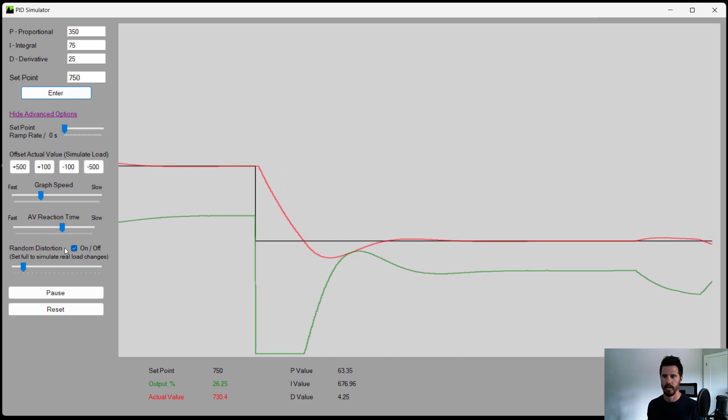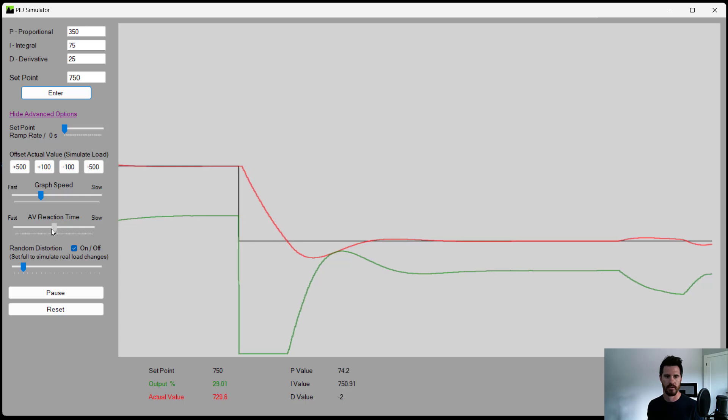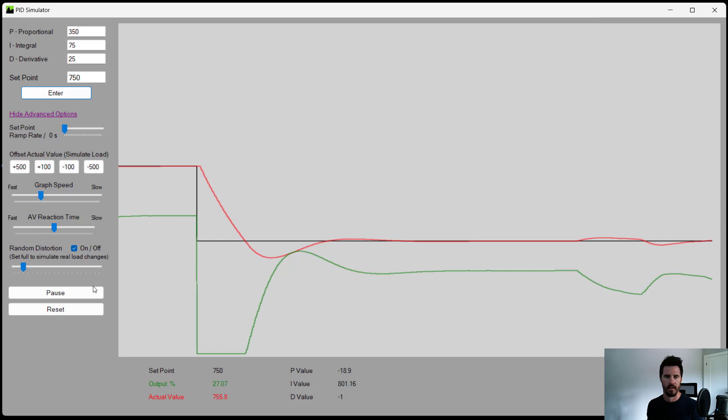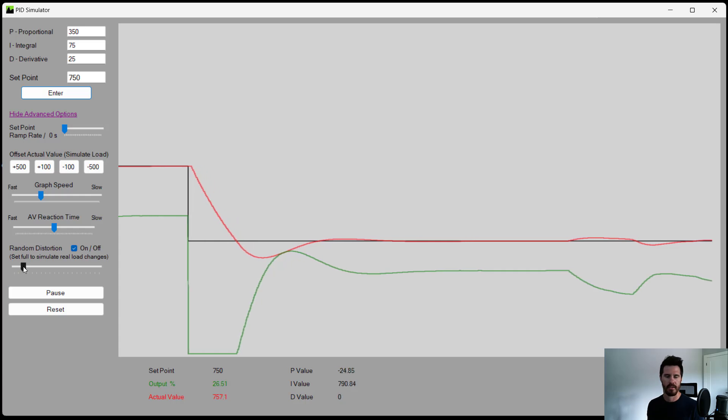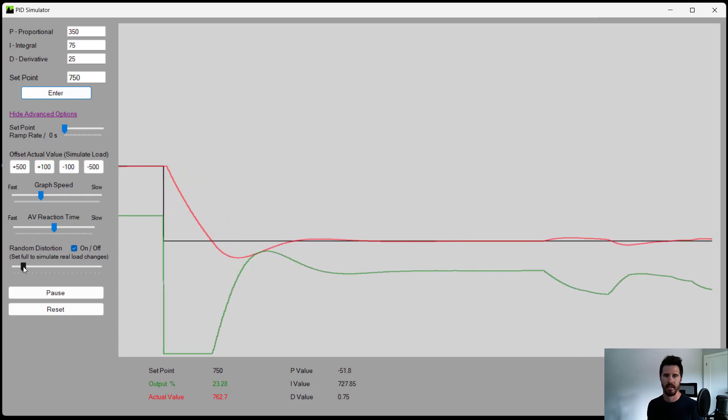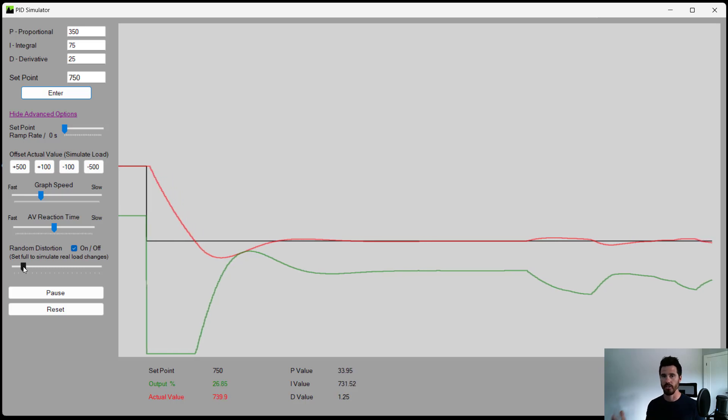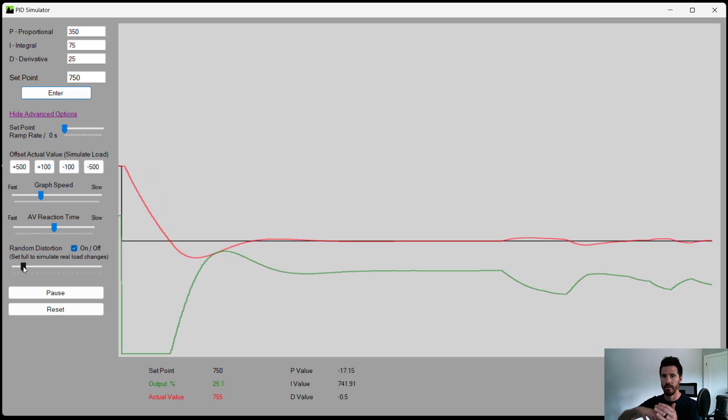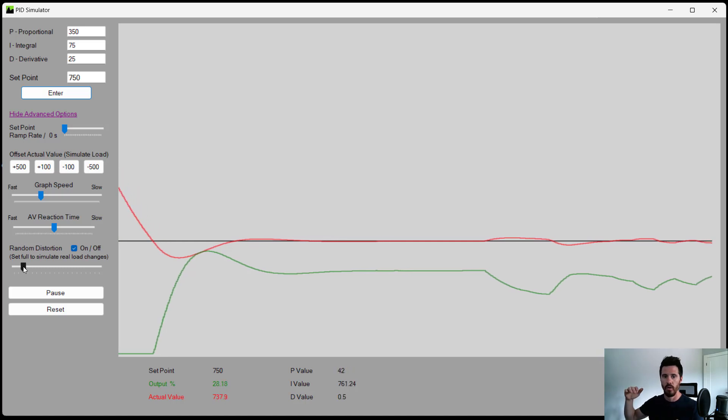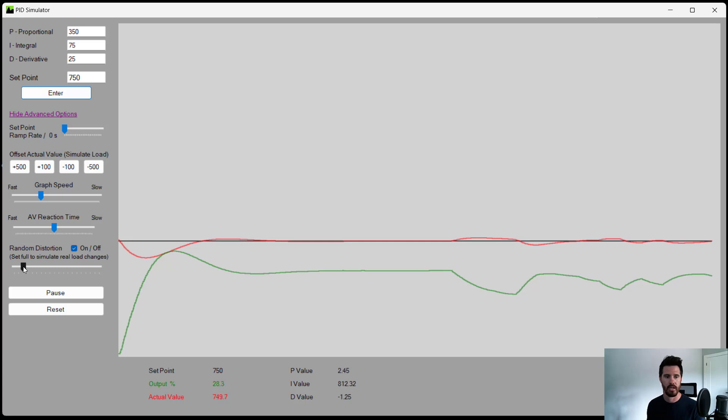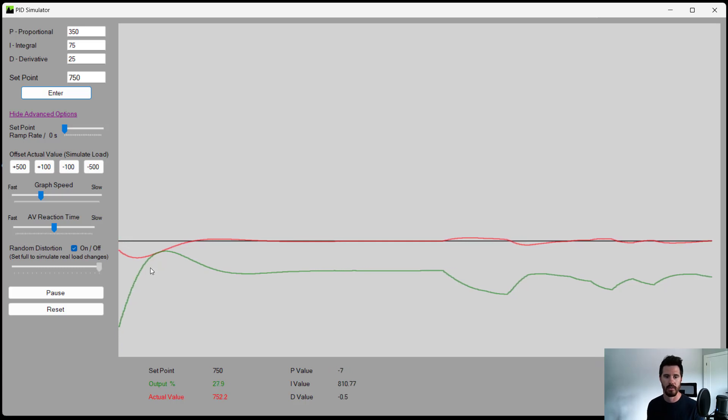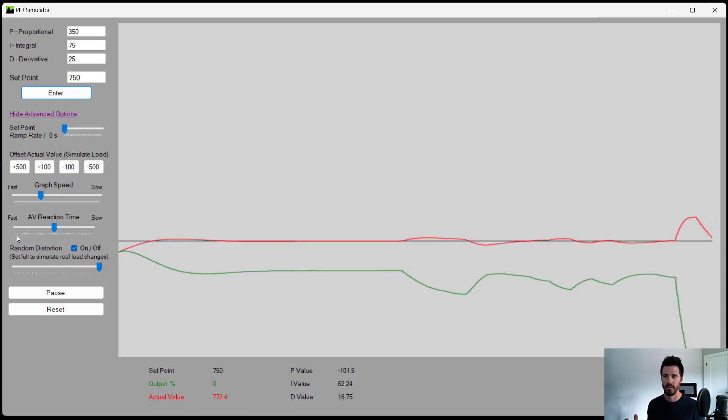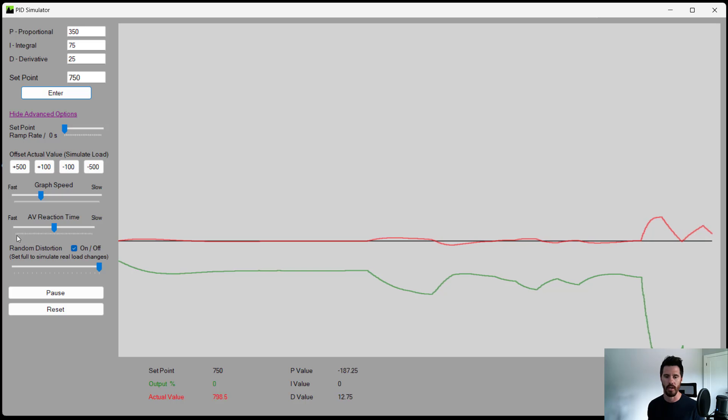Let's make the reaction time a little faster just so for the video's sake so we can see how this thing reacts. Now, one thing that's neat about this distortion tab, if you want to simulate an actual, say, running engine that's trying to, or a generator that's trying to follow the building electrical load or a vehicle that's trying to maintain cruise control while it goes up and down hills, just set the random distortion full. And that'll simulate real load changes so you can see, okay, does my controller actually react to load changes well?